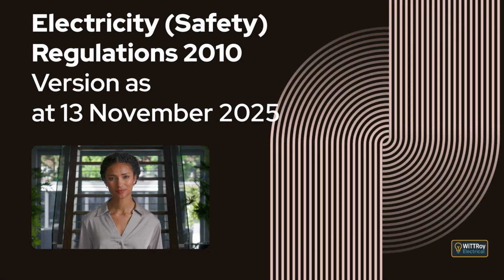Reg 72 are what happens to records of inspection. This regulation explains that a person who issues a record of inspection must provide a copy within 20 working days to the person who contracted the work, or if that person is not readily available, to the owner or occupier of the place or thing where the installation or part installation is located. It also explains that the person must keep a copy, either in hard copy or electronic form, for at least 7 years. The regulation then explains that a copy of the record must be provided within 10 working days if requested by WorkSafe, the board, the registrar, the territorial authority, the person who contracted the work, or the owner or occupier of the place or thing where the installation or part installation is located.